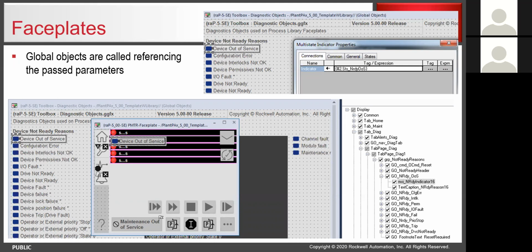And then the addition of the process controllers, which really simplifies the control side, because at that point we're no longer looking at AOIs, they're now embedded in instructions very similar to like a PIDE. They're just embedded in the controller and you use them, drag them in and use them. And now they're firmware managed. So if a year from now we come out with version 6 or 5.1 or something different, it would just be a firmware update on the controller to migrate those forward. Where, currently with all the add-on instructions, we typically use tools and things like that to migrate the code forward.